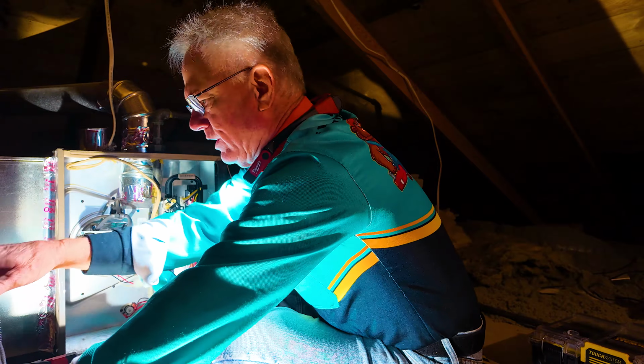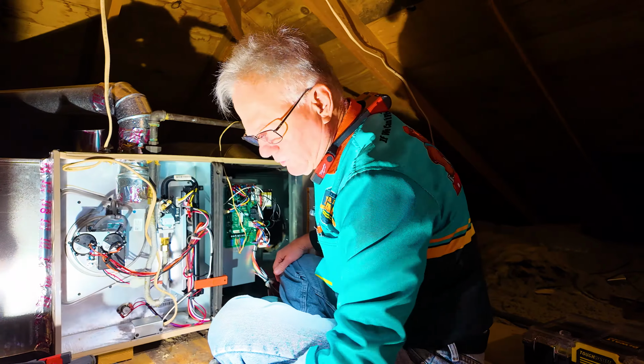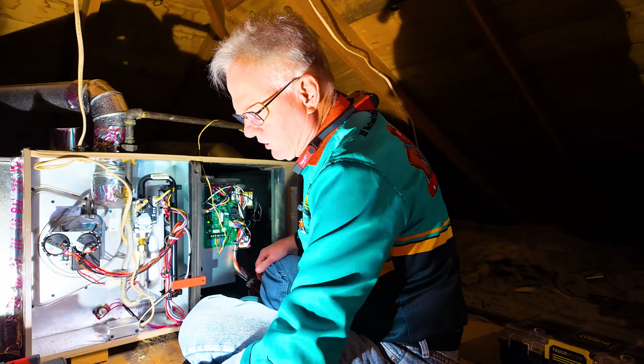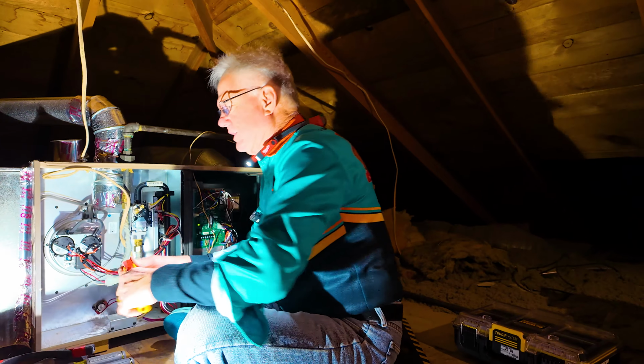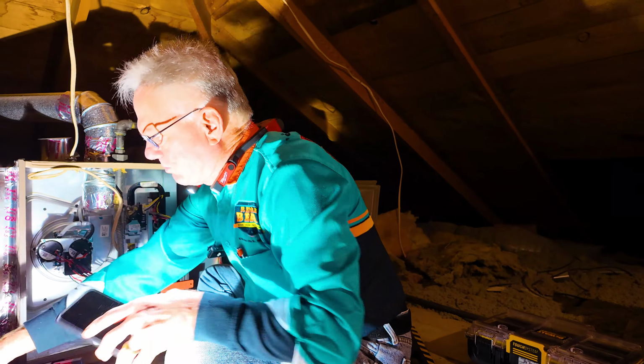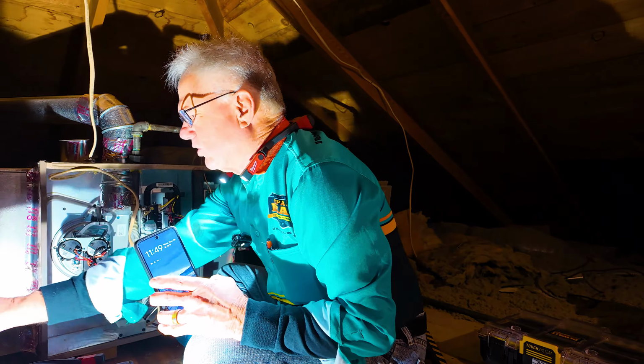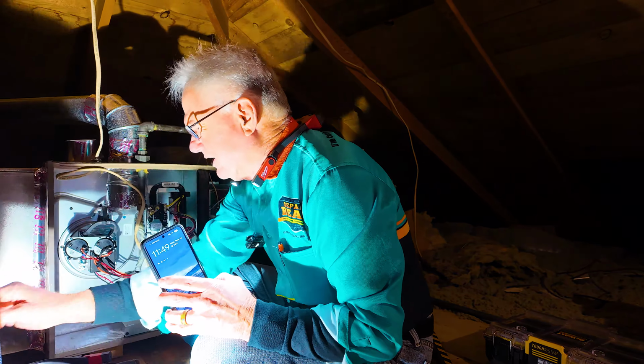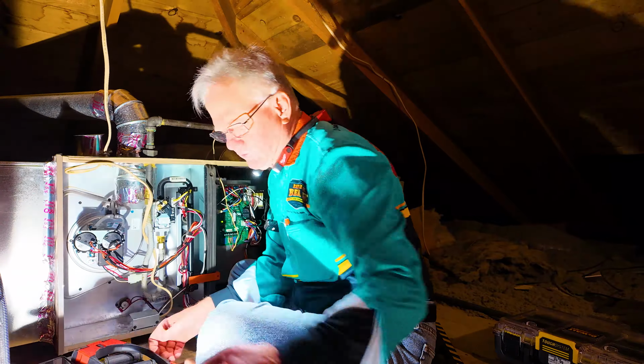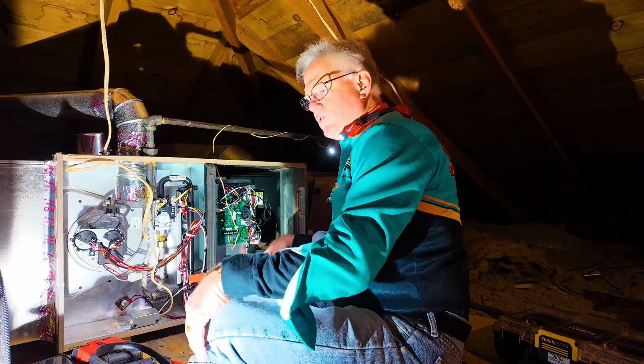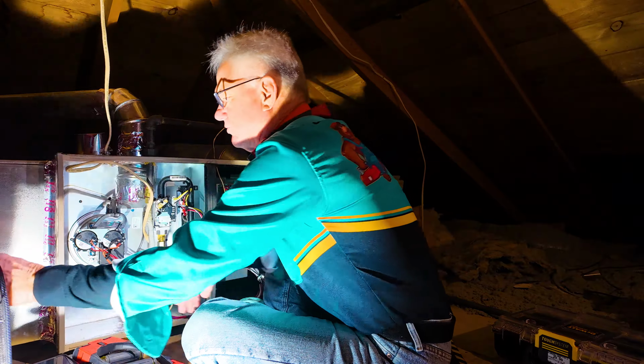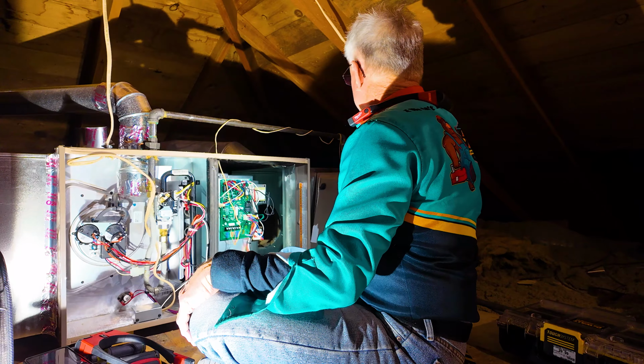I don't see anything else that would indicate a problem. I checked the thermostat already when I first got here to make sure that was functioning right. So it is. So this is the kind of stuff you need to do. This is a relatively new furnace, only a couple years old, and it needs to have maintenance done on it, just like any kind of a part that has combustion or mechanical parts. You need to check it out, because the gas burns, there's dirty stuff in the gas, the natural gas is burning, and that will end up causing it to corrode on top of the flame sensor. And if the flame sensor gets coated with crud, then it can't sense. So now I can take off my override switch there for my manual, and we'll call it a wrap.